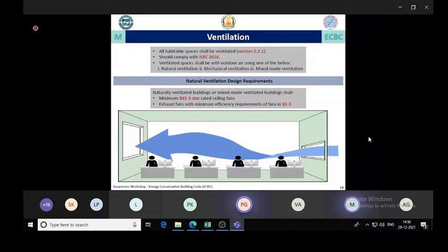Yeah, coming to the mandatory part first, what is the ventilation? So all air-conditioned spaces should have sufficient ventilation, that is fresh air, as per the NBC 2016. So basically, it will be giving you the amount of air changes per hour or the CFM per square feet per person. So those norms need to be complied. And if it is a naturally ventilated building, in that case, again, the NBC norms for naturally ventilated building should be complied, like the percentage of openings. Do we have sufficient openings for ventilation and the height of the ventilation openings? These are all specified in the NBC and they need to be complied.